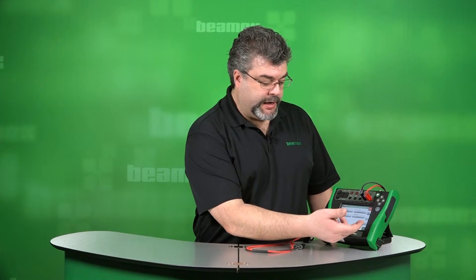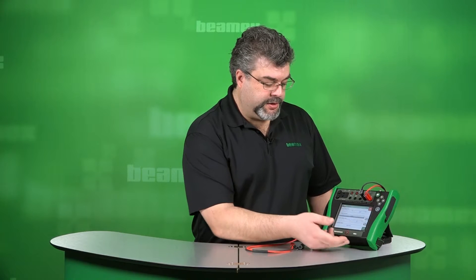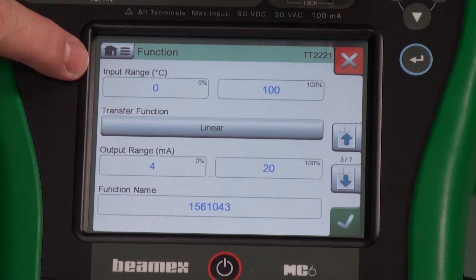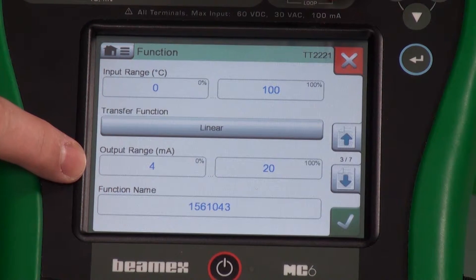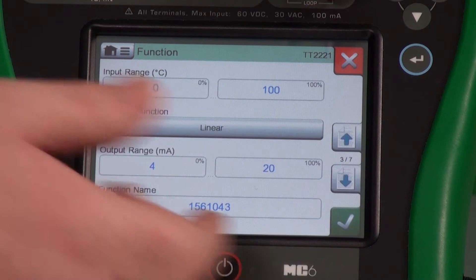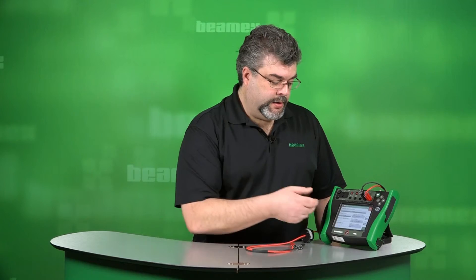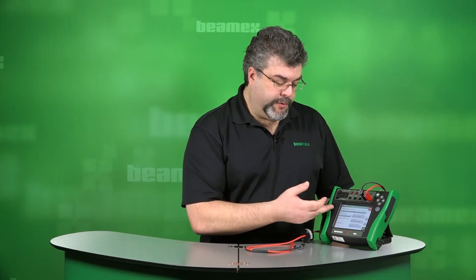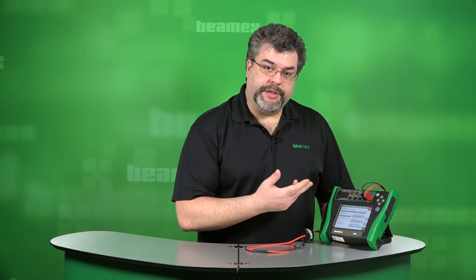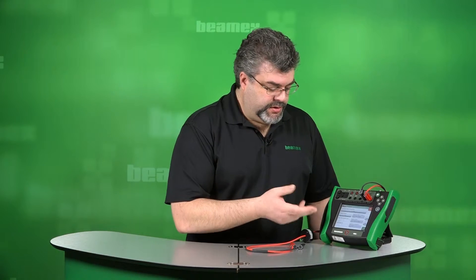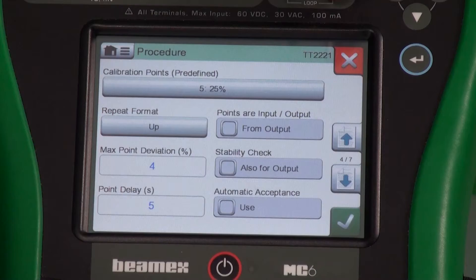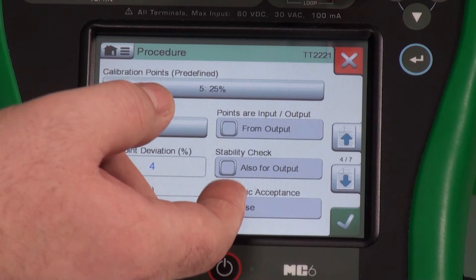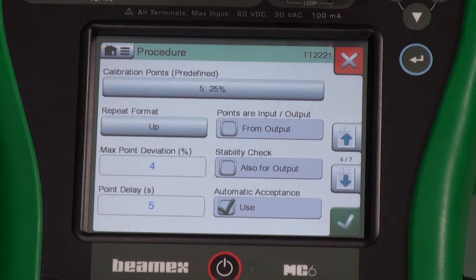We can see that it's 0 to 100 degrees input and 4 to 20 milliamps out. We're set up for a 5-up test strategy, which is fine. If we want this to be an automatic calibration, we tick the box on the bottom — automatic acceptance.